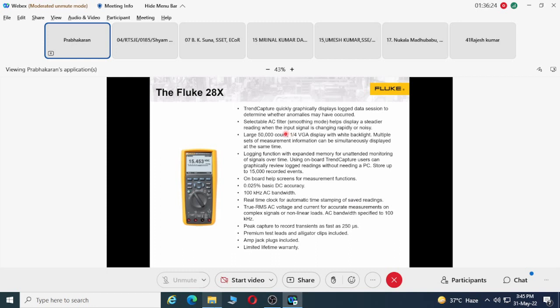And similarly, it is a 50,000 count DMM. It is not a very simple DMM. It can count up to 50,000. That means it gives very accurate readings, like 1.001 or 1.999 kind of voltage you will be able to measure. And similarly, it comes with an accuracy of 0.025%. I think your axle counter test must be of 0.5% accuracy, and this gives you much better accuracies.